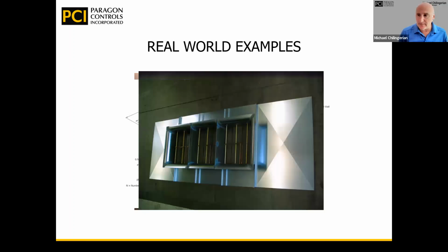Another example of a retrofit. This was a large damper at a very low velocity design. And basically what was happening is once they cracked the damper, all the air would be going in there from the outside air, and it was way too big, not controllable, a poor situation for measurement. So we proposed and installed this one where most of the outside air damper was actually blocked off, and we reduced the area so that it became manageable for the damper, as well as a better measurement situation for the outside air. So it's not just what the unit is, it's what we can bring to the job also.